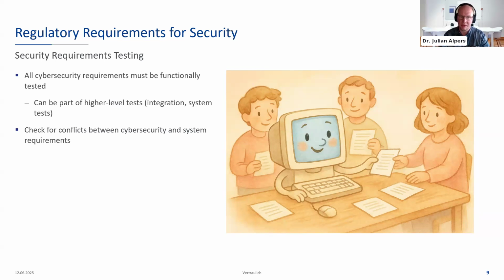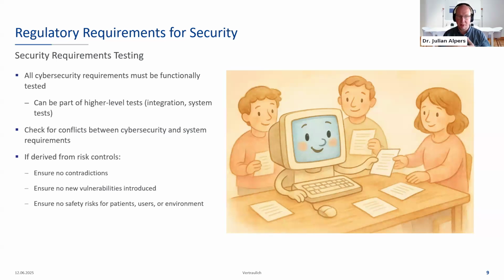You need to check for conflicts between cybersecurity and other system or stakeholder requirements, because cybersecurity requirements, more than other requirements, may contradict other requirements, like stakeholder requirements or requirements from the safety risk management. So you need to assess them and make sure that you have a good reasoning why you follow one requirement more than the other. And if derived from risk controls, you need to ensure, obviously, that your new risk mitigation measures or requirements do not contradict each other, that they do not introduce new vulnerabilities, and you have to ensure that there are no safety risks for patients, users or environment.